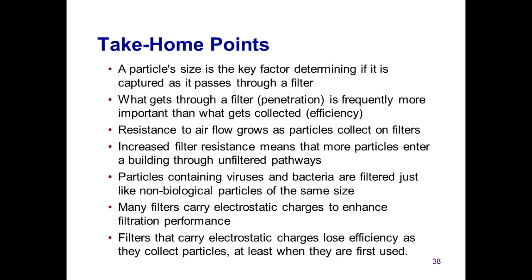Let's summarize the most important points from the talk. A particle size is the key factor determining if it is captured as it passes through a filter. Frequently, and in particular as you think about trying to protect swine, what gets through or around a filter is more important than what gets collected. This requires a slightly different mindset than thinking only about what gets captured on filters. Resistance to airflow increases as particles collect on a filter, and that increased resistance means that more particles are going to enter a building through unfiltered pathways. This is particularly the case for swine buildings.